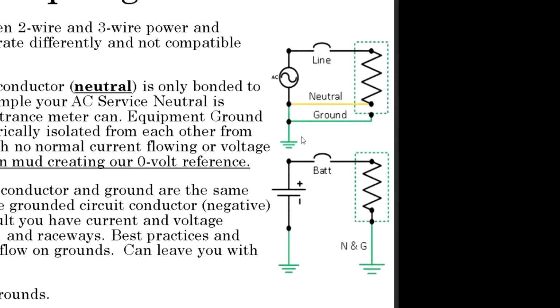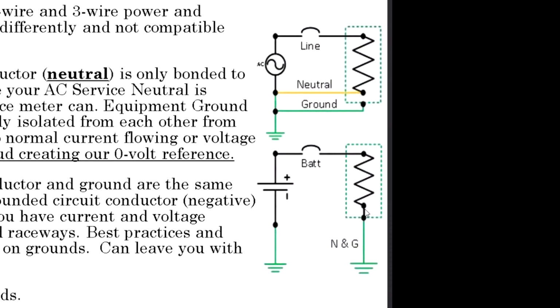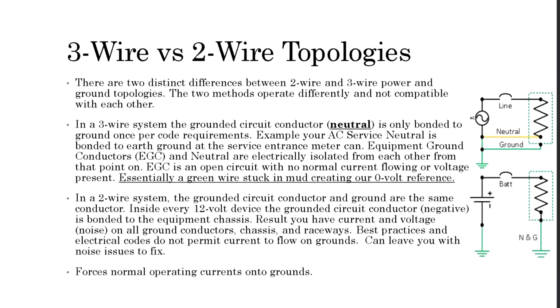Now we drop down here and contrast that to a two-wire system. The grounded circuit conductor and ground are essentially the same conductor. Inside every 12-volt device, the grounded circuit conductor, the negative, is bonded to the equipment chassis. The result is you're going to have current and voltages on all conductors, chassis, and raceways. Best practices and electrical codes do not permit current to flow on grounds. It can leave you with noise defects, and you're forcing normal operating currents on the grounds.